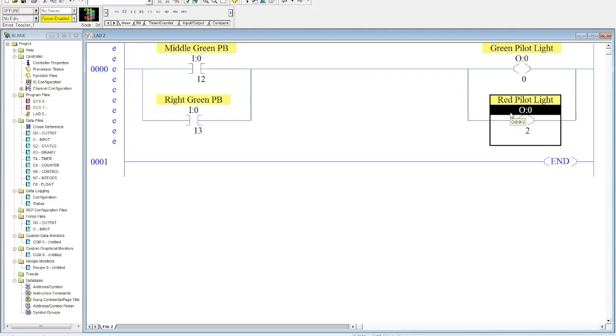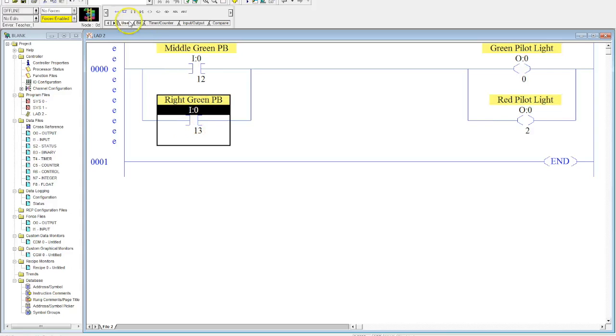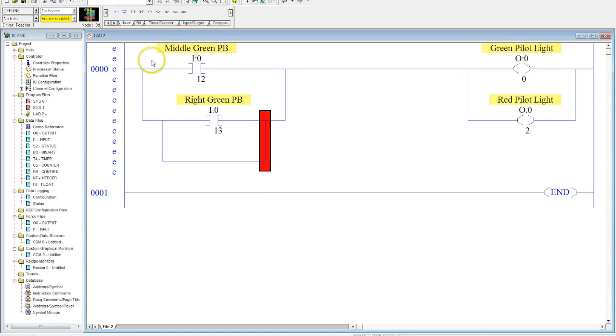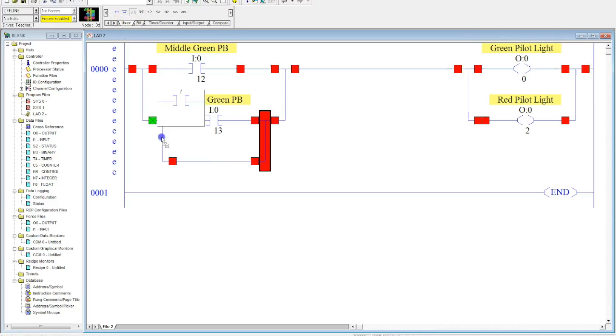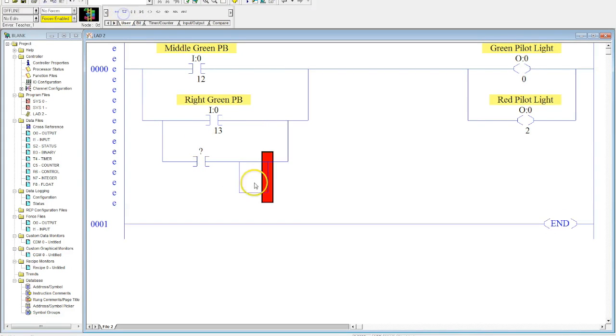But before I do that, I want to show you how to put a third input in parallel. And there's a couple of tricks to this, so I want to make sure that we don't do a way that will kind of annoy your employer later. So, let's say I wanted to put a branch around here. I highlight this, I highlight my bottom input, I select my rung branch again, comes over here, drag it over here. Now, what I end up getting is an upside down wedding cake. And if you start putting a lot of inputs, if there's a lot of logic to turn on your output, you're going to end up with this gigantic, huge, upside down wedding cake.